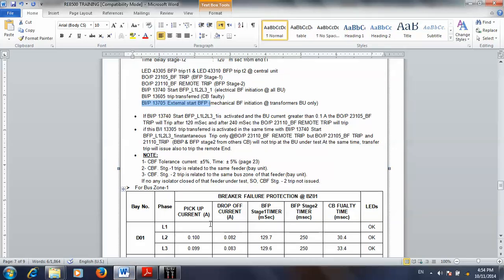by the same way you can test your function, but here without current. Here by circuit breaker status, one time you will give the binary input and the circuit breaker status is open, and the other time you will give the binary input and the circuit breaker is closed, and you can inject this binary input through the Freja outputs, and in page 1 and page 2 you put the current and voltage, everything is 0, and only the test is through binary input.